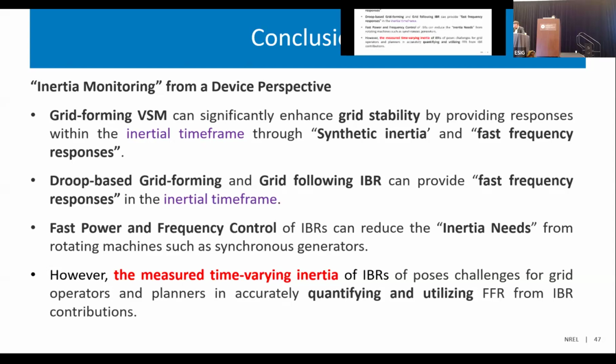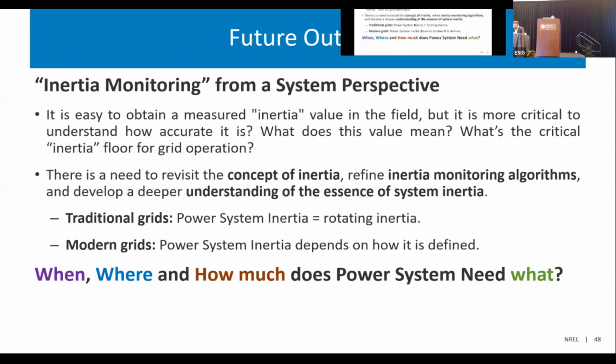However, the time-varying inertia poses a big challenge for grid operators and planners — we need to understand how to use these numbers in system operation. This leaves us with more questions from a system perspective: once you have a measurement or a value, it's more critical to understand how accurate it is and what that value means, and how to develop a critical inertia floor for grid operation 24/7. I think it's more important to revisit the concept of inertia, refine inertia monitoring algorithms, and develop a deeper understanding of system inertia.